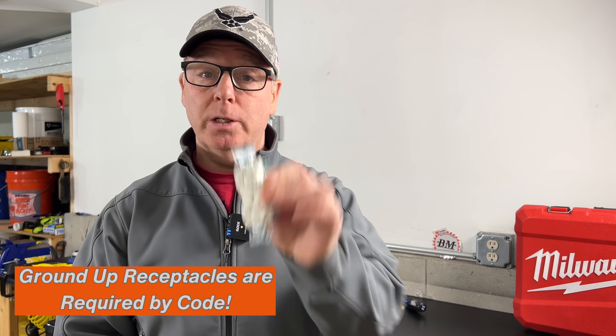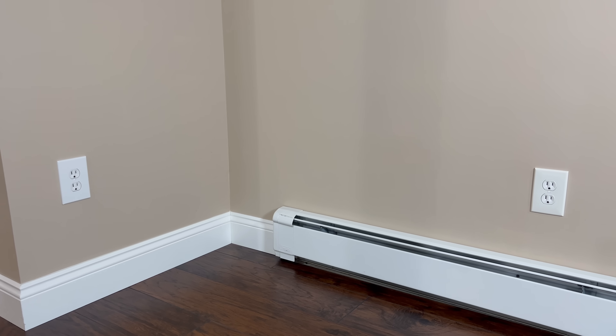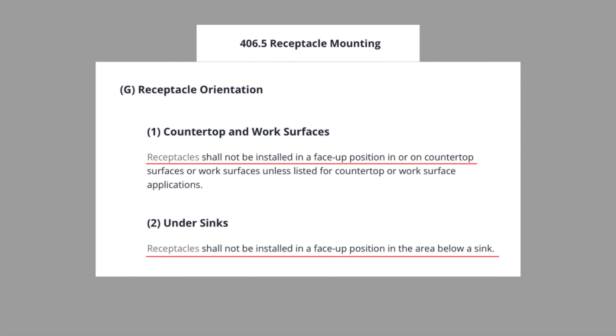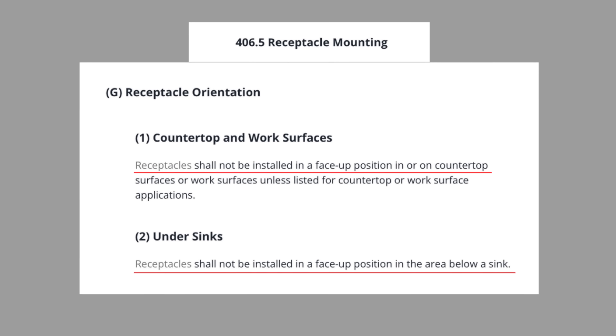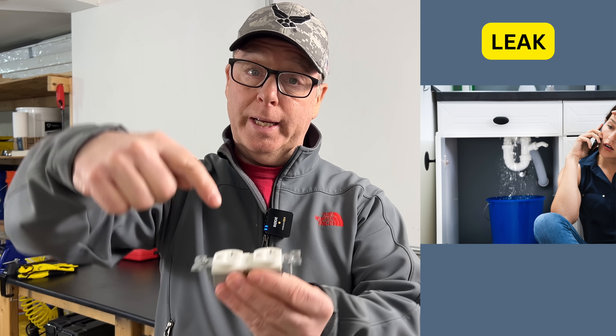False claim number two: ground-up receptacles are required by code. The NEC does not specify receptacle orientation, and neither do the receptacle manufacturers or NEMA. The only reference to orientation mentioned in the code is in article 406.5(G), which prohibits standard receptacles from being installed in the face-up position in countertops or in the area below a sink. This actually makes a lot of sense — a leak or a spill flowing into a face-up receptacle could be hazardous.